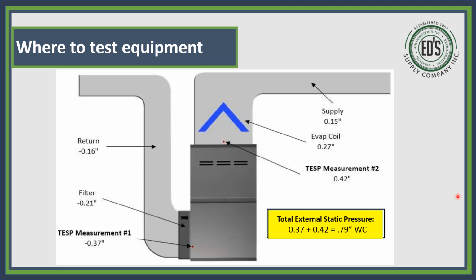So on this drawing, we kind of did that, and you can see here's our return. If you could see the airflow, it's coming in and hitting here, but because we have a radius throat and a radius heel, there's not a lot of hitting and building up. It's going to actually flow around these corners, all right? So you're going to have less drag and resistance coming down, less drag and resistance coming in here. We're still going to put our probe right here in the side of the furnace. You don't have to do it in the door. You can put it in the side. If you want to, you can put it in the door, but it needs to be on this side of that filter. And then here was where we were talking about that coil.